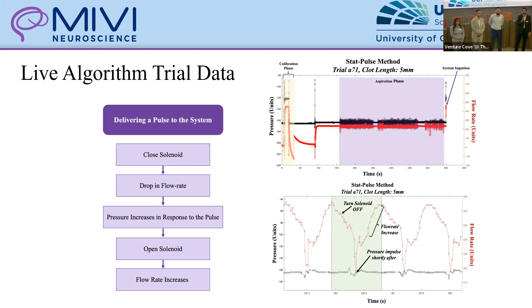So let's take a look at this in more detail. Here we have one of our algorithms, the stat pulse algorithm, that takes into account 12 data points and compares it with a specified flow rate threshold. If it's below that threshold, then the solenoid valve will close, which causes an increase in pressure and a decrease in flow rate to the minimum value. Once we open the solenoid valve again, we have a large pressure differential. And so as a result, if we have a large pressure differential, it should theoretically improve volumetric flow rate. And so as a result, an increase in volumetric flow rate reduces clot aspiration time.